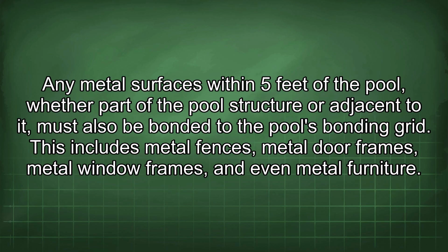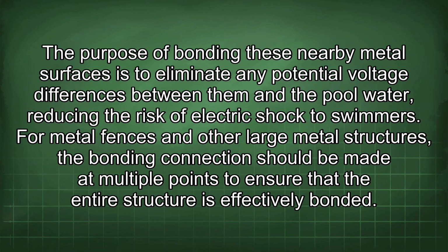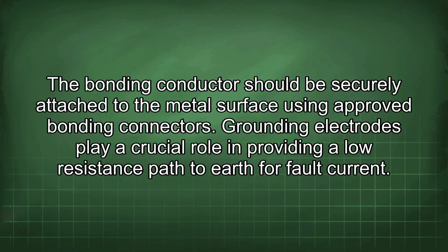Any metal surfaces within 5 feet of the pool, whether part of the pool's structure or adjacent to it, must also be bonded to the pool's bonding grid. This includes metal fences, metal door frames, metal window frames, and even metal furniture. The purpose of bonding these nearby metal surfaces is to eliminate any potential voltage differences between them and the pool water, reducing the risk of electric shock to swimmers. For metal fences and other large metal structures, the bonding connection should be made at multiple points to ensure that the entire structure is effectively bonded. The bonding conductor should be securely attached to the metal surface using approved bonding connectors.